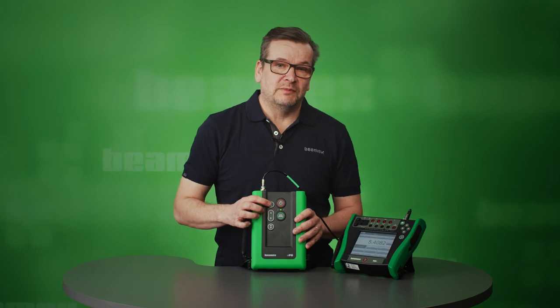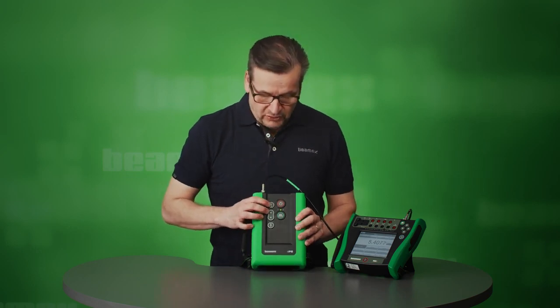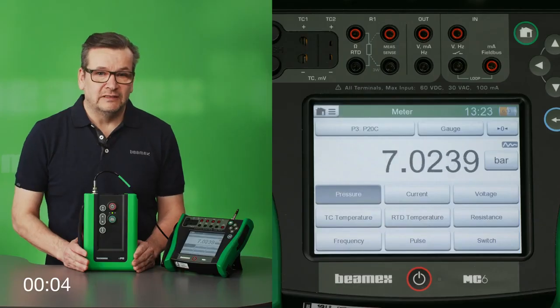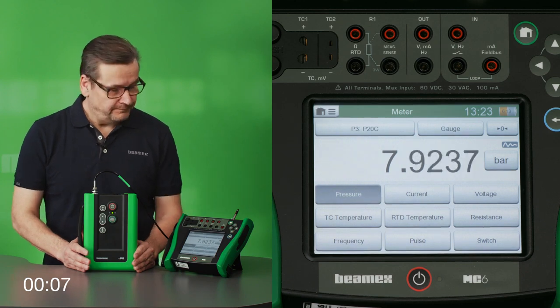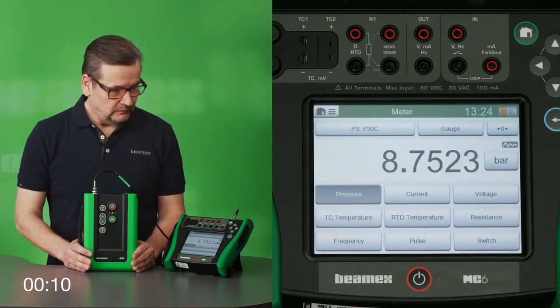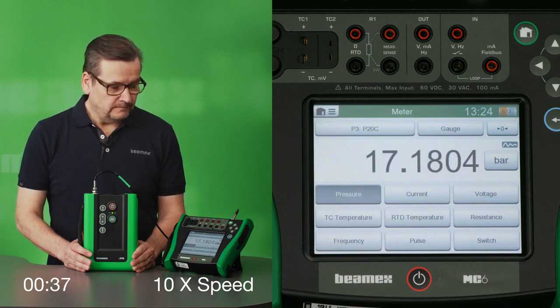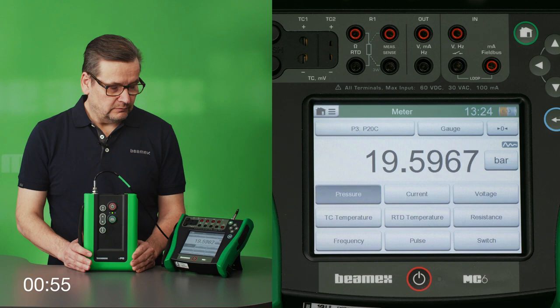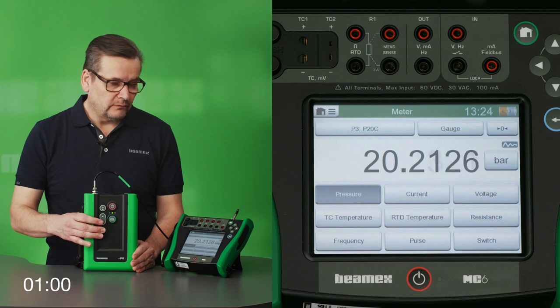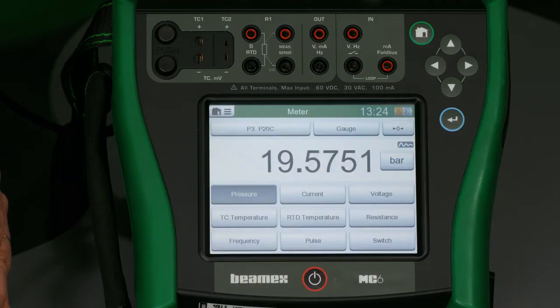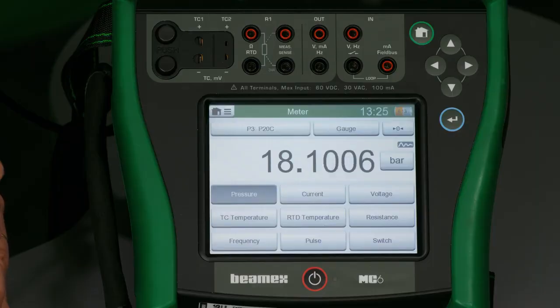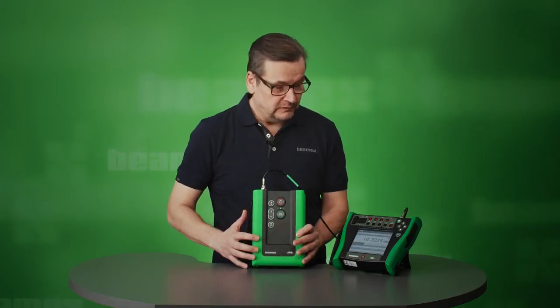But let's go a bit higher. The ePG can go up to 20 bar or 300 psi, so you can also lock the up keys and you don't have to hold the buttons. So let's see how it goes to 20 bar. So now we reach the 20 bar. We can come down with the fast down button or with the fine adjustment down button. Or we can vent the system by pressing the vent and come down to 0.